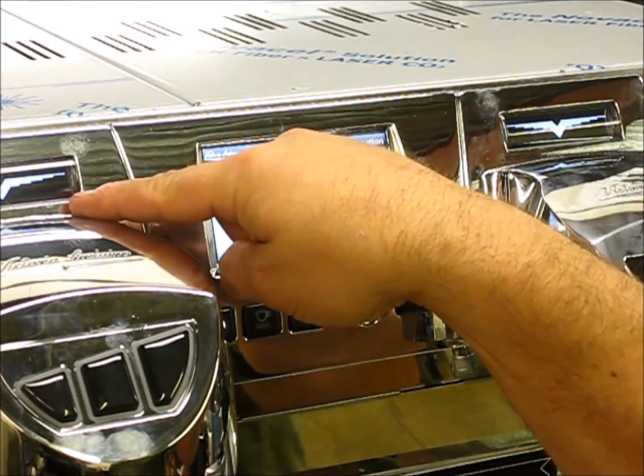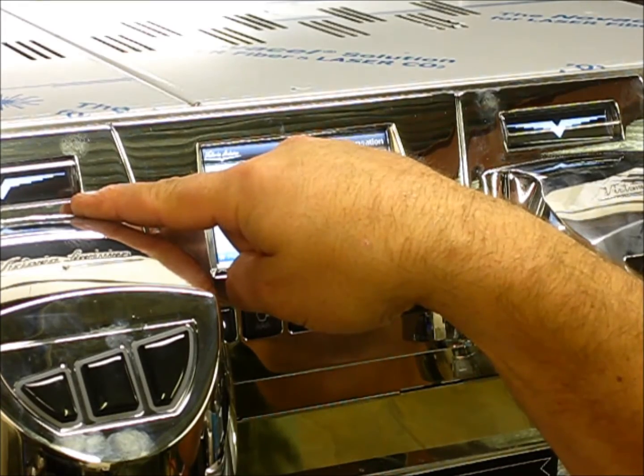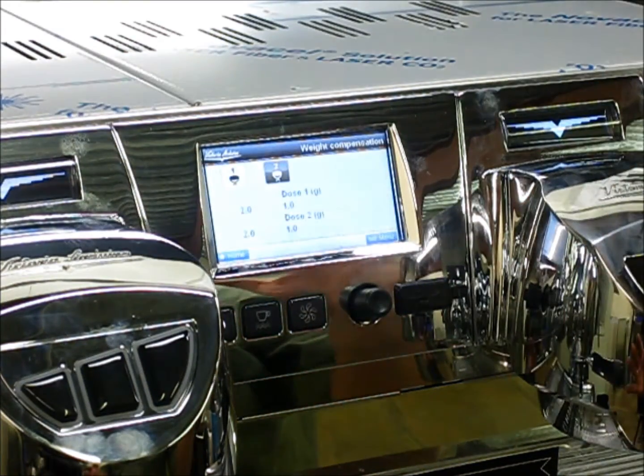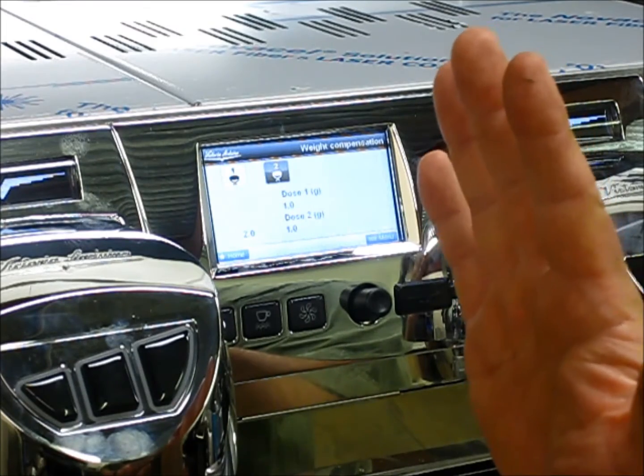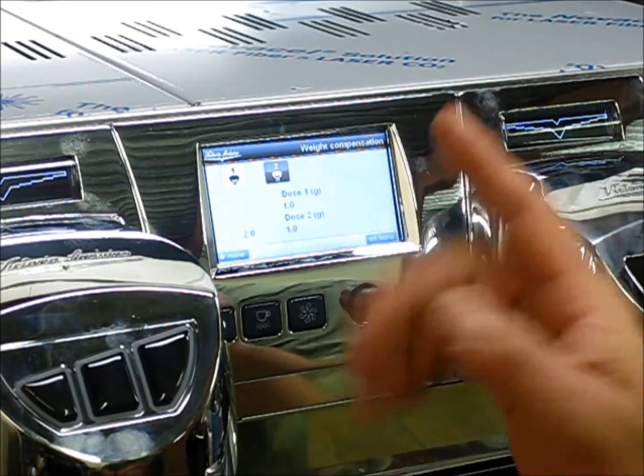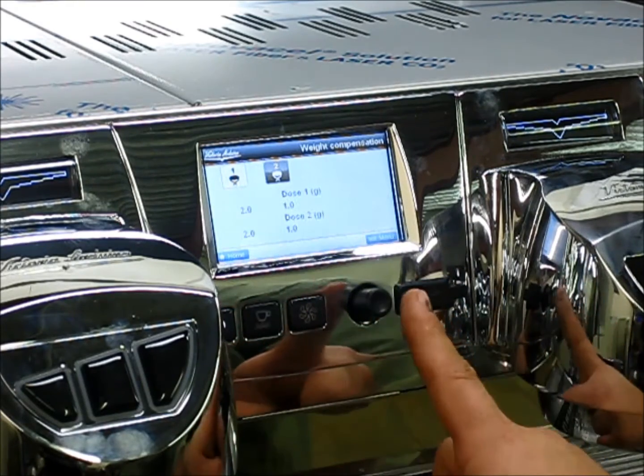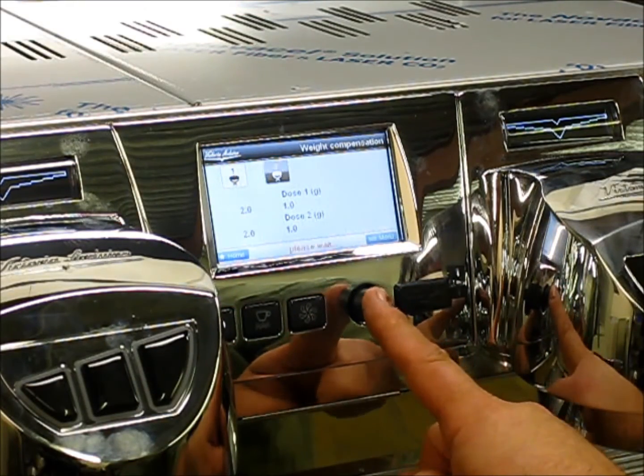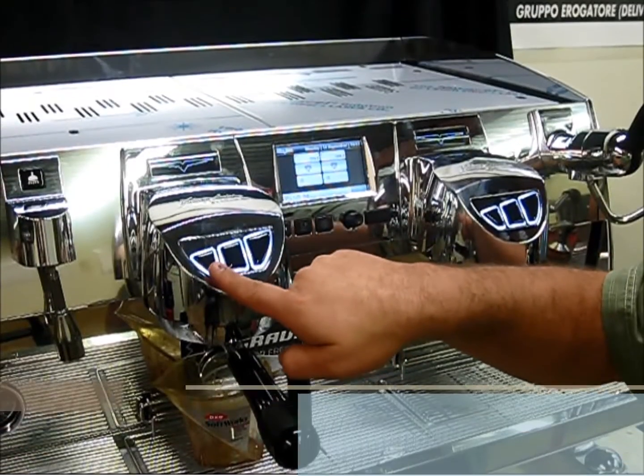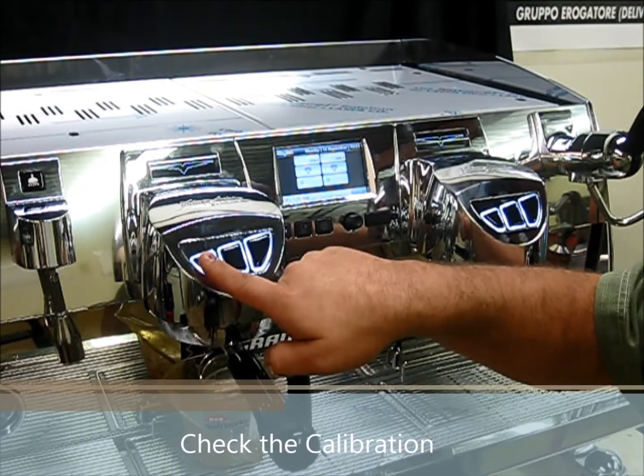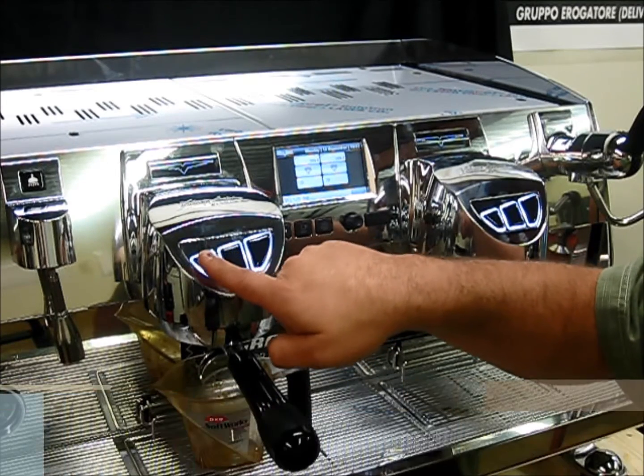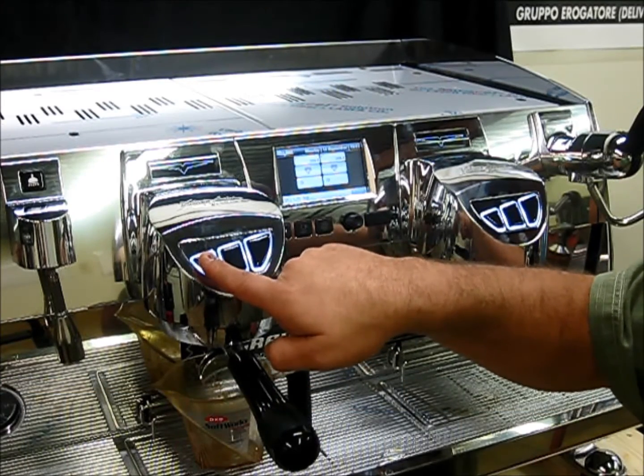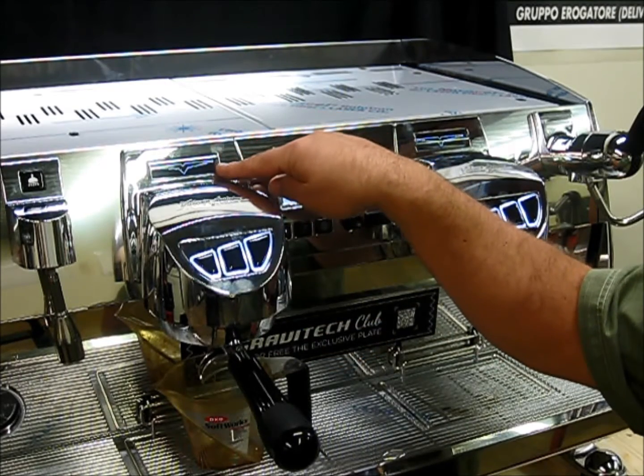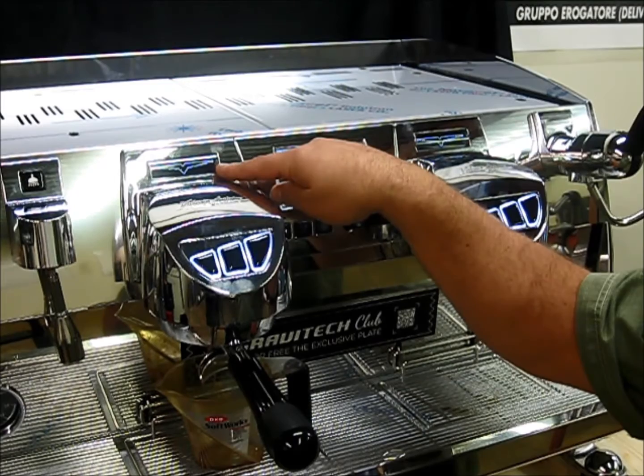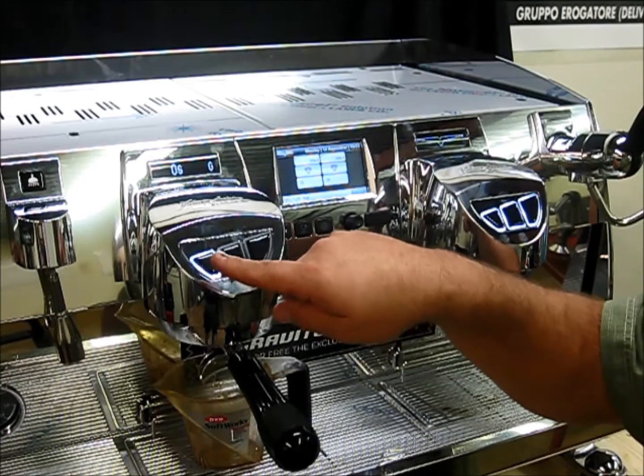We obviously saw that our value on the screen earlier was higher, so we want to bring the scale more into line with the Acaia scale, our controlled scale. So now we've inputted the value, and we are going to enter that. Now we're going to select button 1, which we know is programmed for 30 grams. As you saw earlier, we went into weight compensation because we wanted the value on the screen to be the same as our controlled scale, the Acaia scale. So right now, we're going to check that.